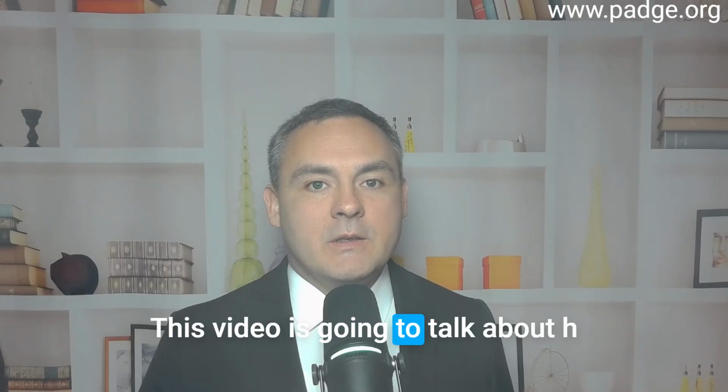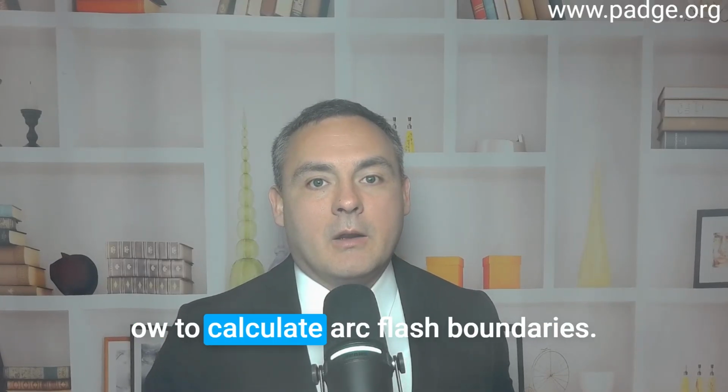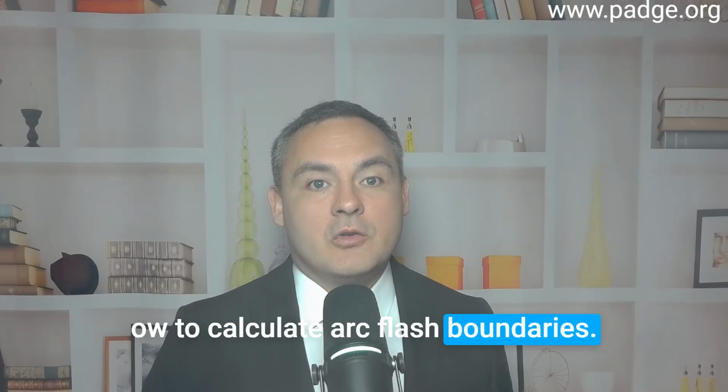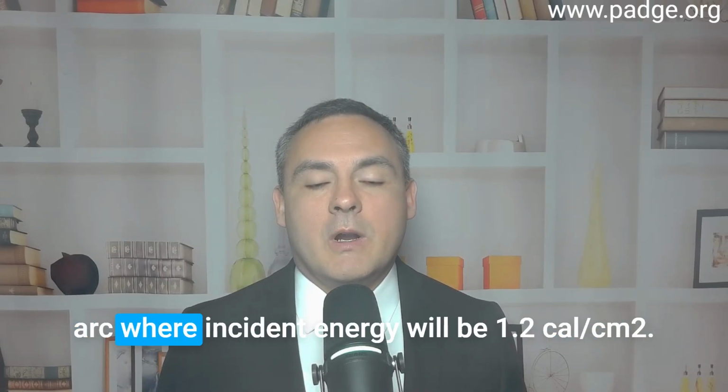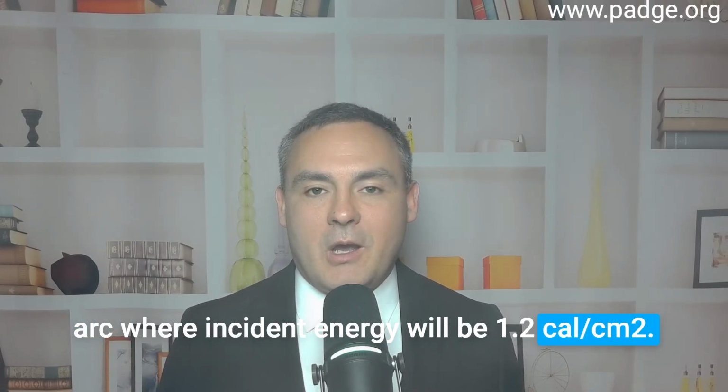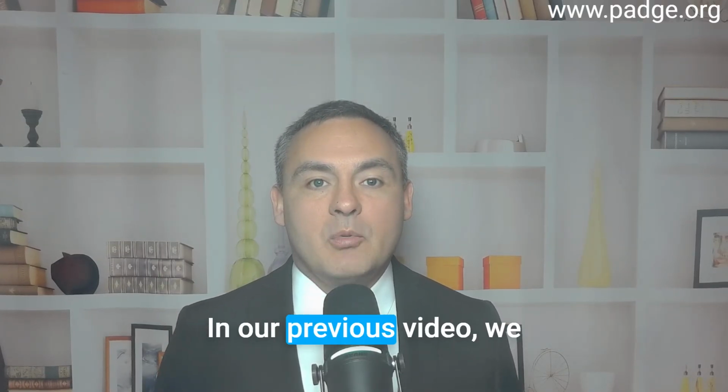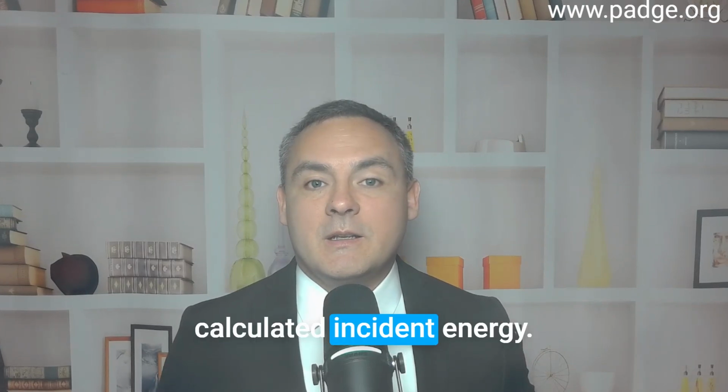This video is going to talk about how to calculate arc flash boundaries. The arc flash boundary is the distance from an arc where incident energy will be 1.2 calories per centimeter squared. In our previous video, we calculated incident energy.